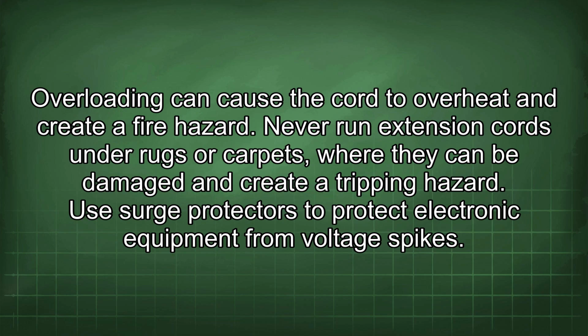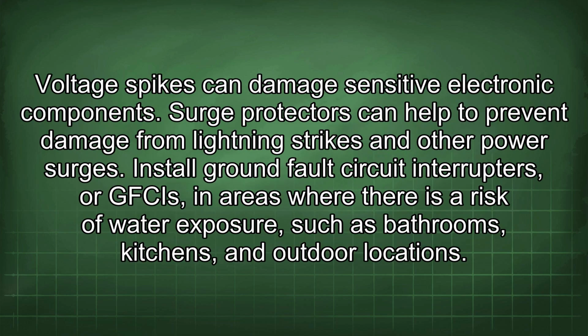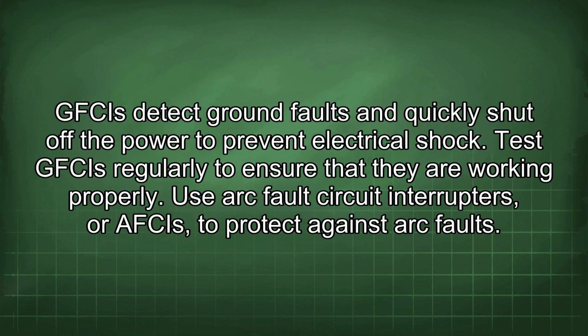Use surge protectors to protect electronic equipment from voltage spikes. Voltage spikes can damage sensitive electronic components. Surge protectors can help to prevent damage from lightning strikes and other power surges. Install ground fault circuit interrupters, or GFCIs, in areas where there is a risk of water exposure, such as bathrooms, kitchens, and outdoor locations. GFCIs detect ground faults and quickly shut off the power to prevent electrical shock. Test GFCIs regularly to ensure that they are working properly.